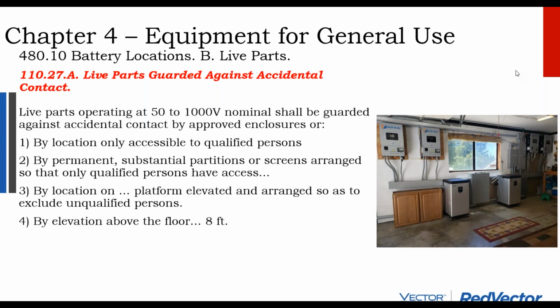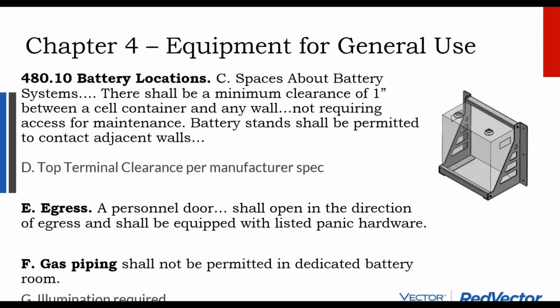So you could have your exposed terminal batteries as long as they're caged off, or what is far more common is to buy a higher end manufacturer assembled system where the battery terminals are already protected by the battery assembly itself. You can elevate the batteries above the floor. 8 feet is the typical one. If you elevated them less than 8 feet, then you have to treat it like a locked cage. So, basically, if you want to put your batteries in the garage and you're buying just the battery and not something more top shelf, you're going to have to cage it off. So do-it-yourselfers be warned, you can't just buy a homemade battery with exposed terminals and keep it on a shelf. You'll be liable for that.